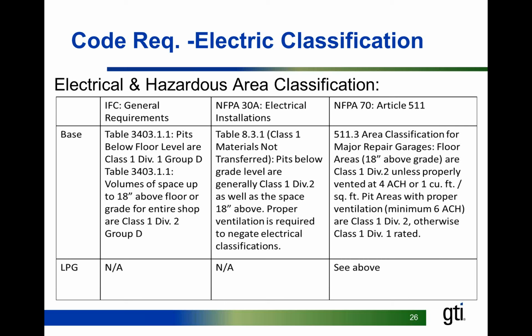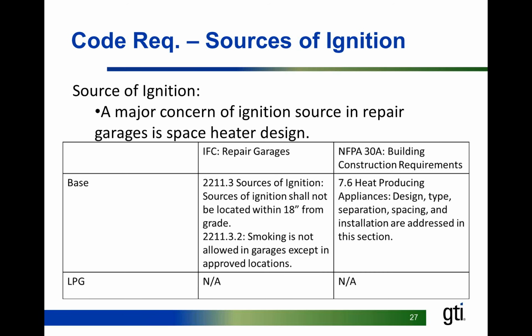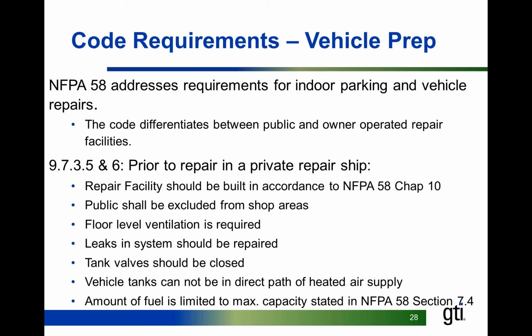Sources of ignition are a concern as well, but because the gas is heavier than air, it has different requirements. The concern is near the floor again, so there are no additional code changes for propane. Vehicle prep, there are some differences because the fuel in the vehicle is stored at a lower pressure, but still in the hundreds of psi area. So there are concerns there. Code dictates that you should shut off the valve on the fuel tank. Leaks need to be checked and made sure that there are no leaks in the system. NFPA 58 is the major U.S. federal code that covers propane. Chapter 10 has a lot of good details on that.